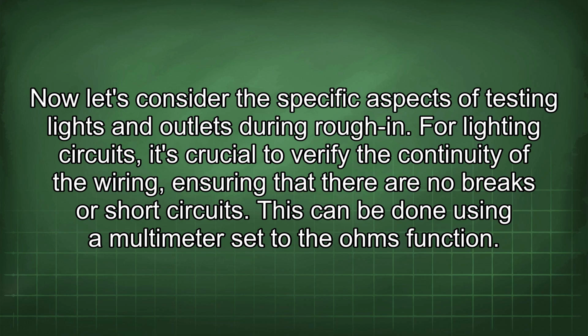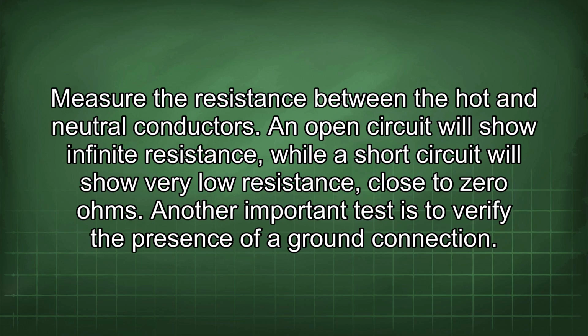For lighting circuits, it's crucial to verify the continuity of the wiring, ensuring that there are no breaks or short circuits. This can be done using a multimeter set to the ohms function. Measure the resistance between the hot and neutral conductors. An open circuit will show infinite resistance, while a short circuit will show very low resistance, close to 0 ohms.